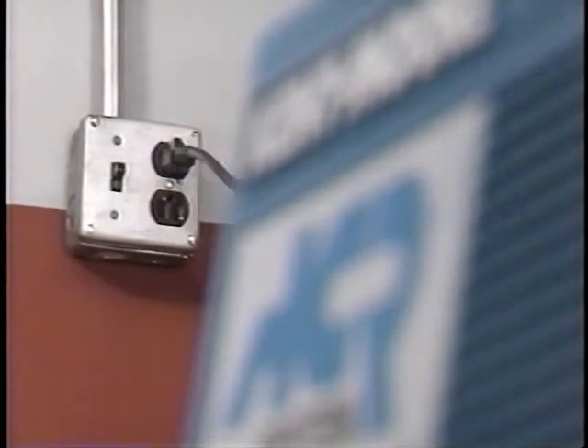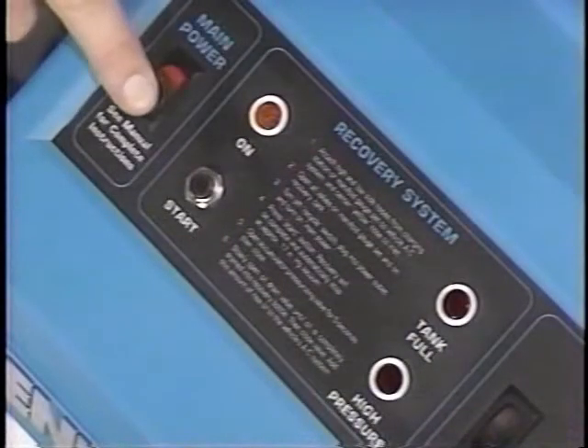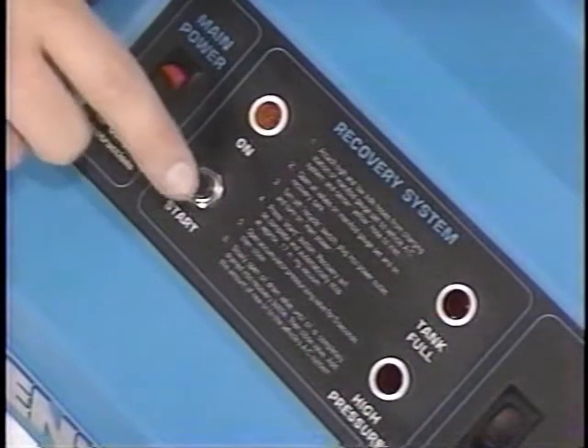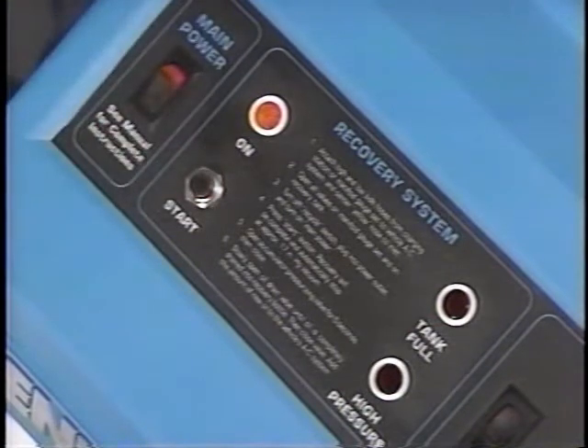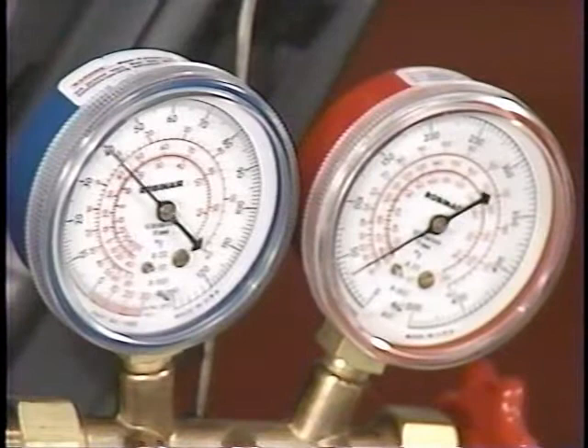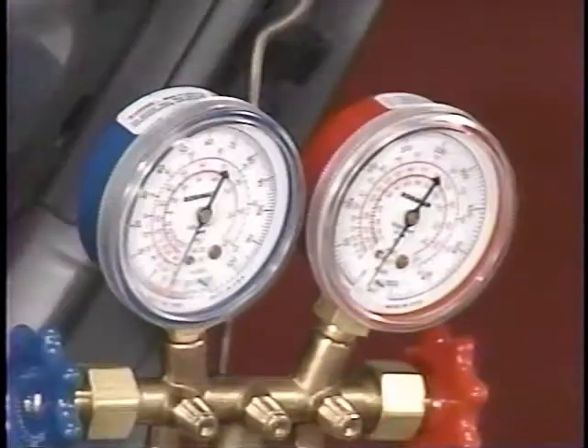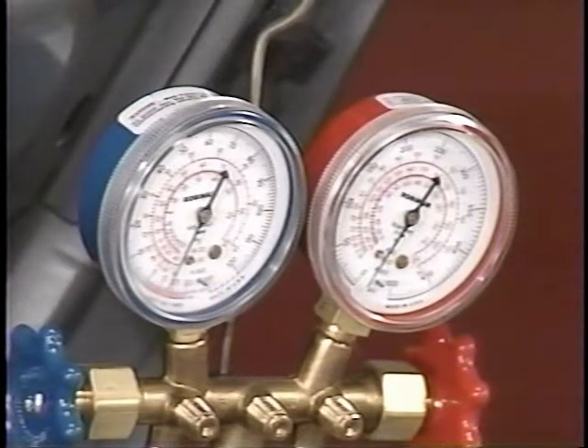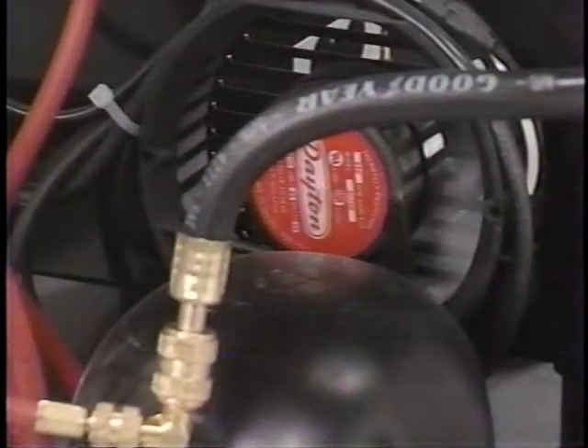Plug the ACR3 system into a standard 110-volt AC outlet. Turn on the main power switch. Push the compressor start switch. The compressor on light should illuminate. After about 8 minutes, the recovery pressure switch should detect a vacuum of 17 inches of mercury and automatically shut off the compressor. The fan, however, continues to run to cool the recovery compressor.